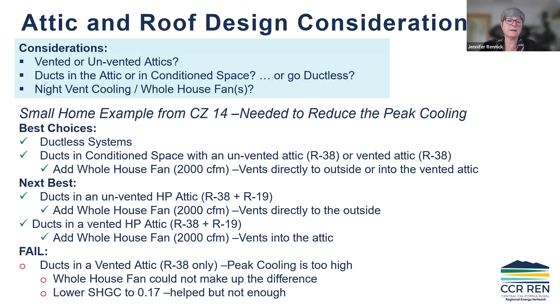In this case, even though in past times this project would have passed under the other codes, now with the peak cooling requirement, just having ducts in a vented attic with only ceiling insulation doesn't work. Even adding a whole house fan and dropping the solar heat gain coefficient on the windows helped, but it wasn't enough to curb that peak cooling. So the big strategies now for passing our energy code on new construction really involve looking at ductless systems and ducts in conditioned space.